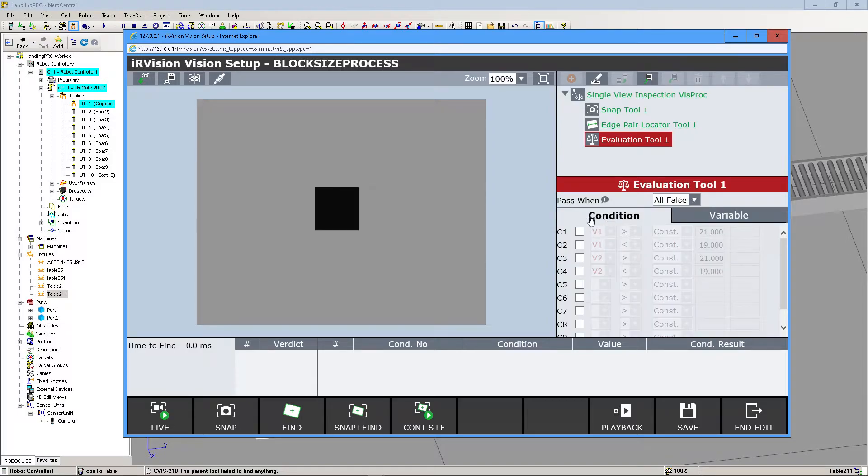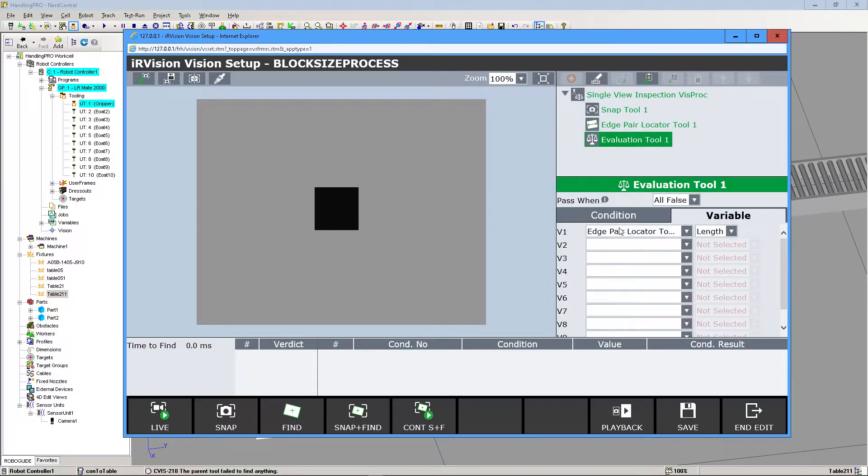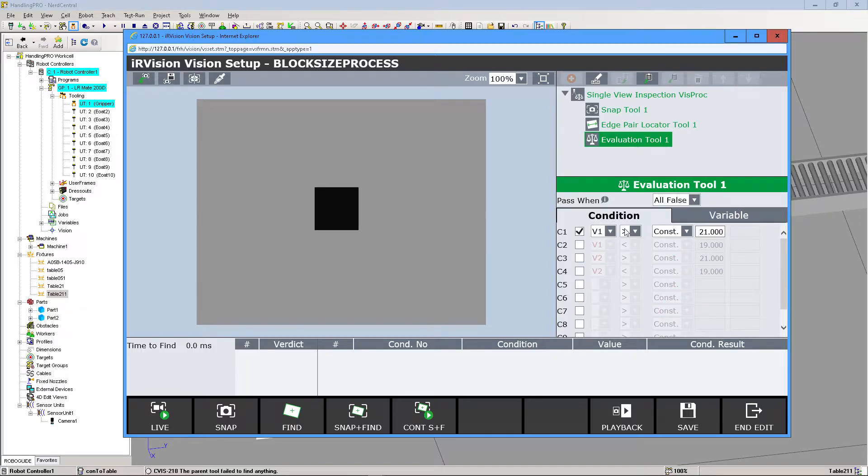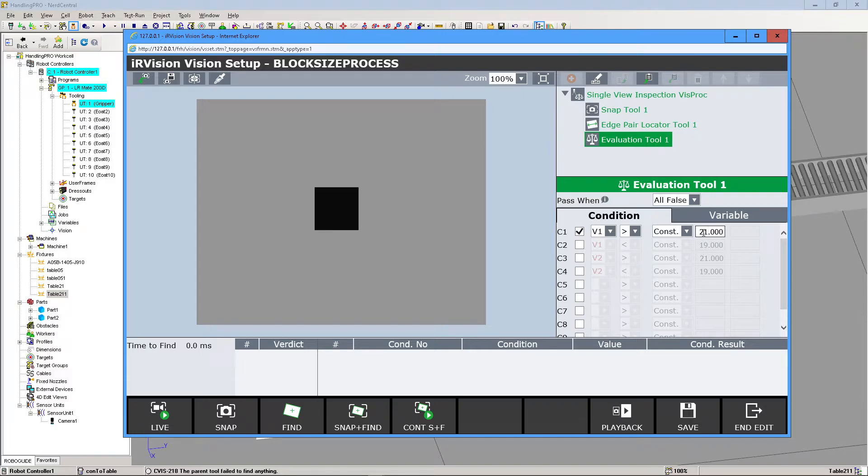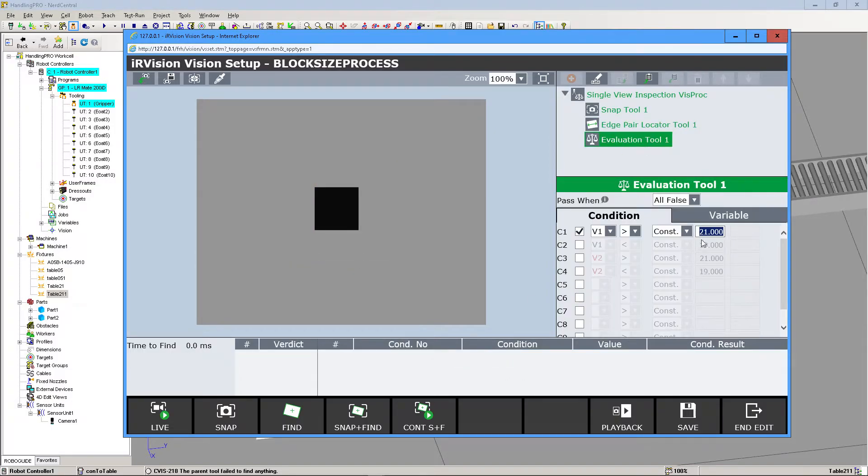We go under Condition. I've already messed around with it, so just ignore these. We're going to go through it one by one. Under Condition 1, we're going to link it to Variable 1 and make it Greater Than. We're assuming a plus or minus 1 millimeter offset. Since this block is 20 millimeters, even though the tool measures it at 19.955, that's pretty close to 20. So if it's greater than 21, we want this to fail.